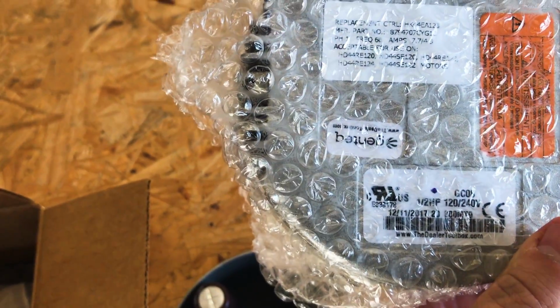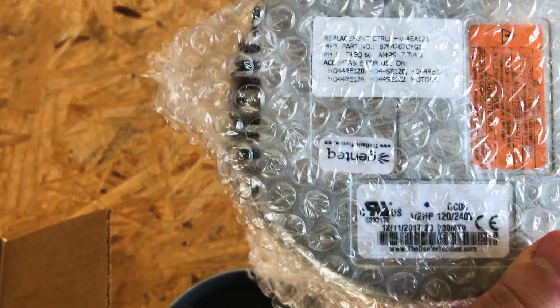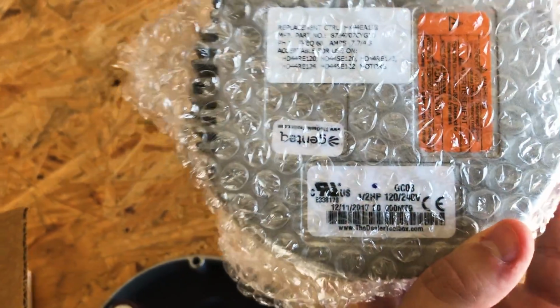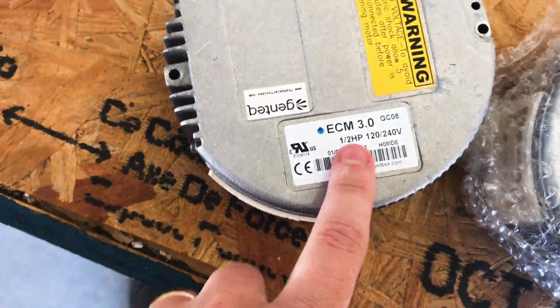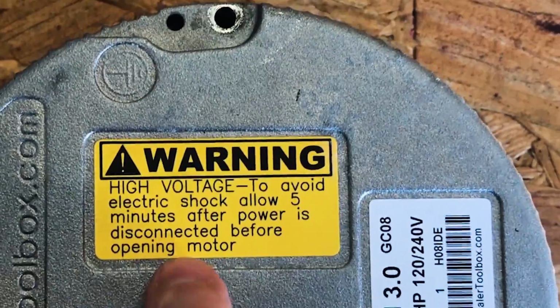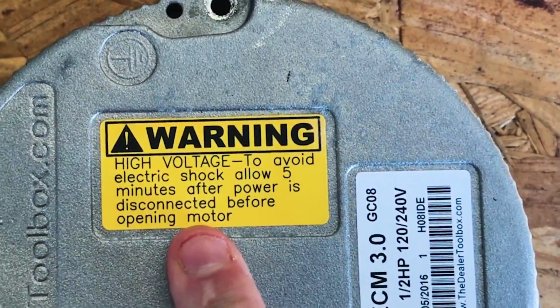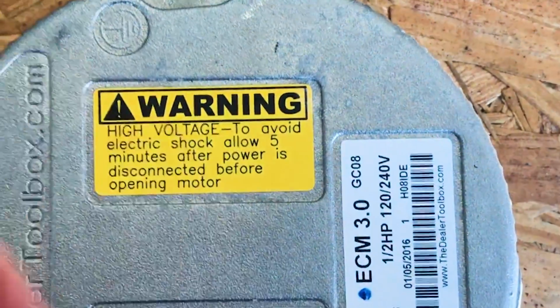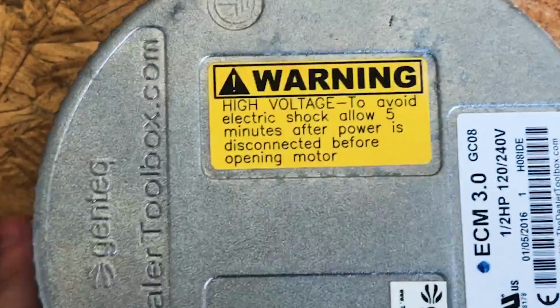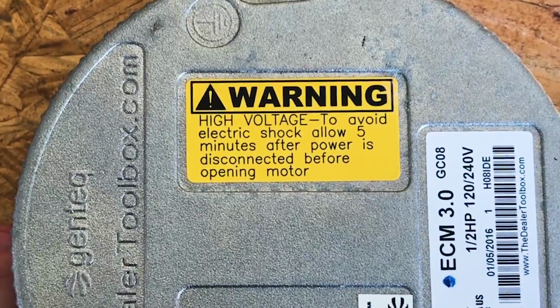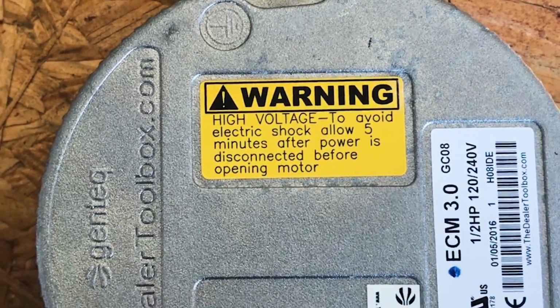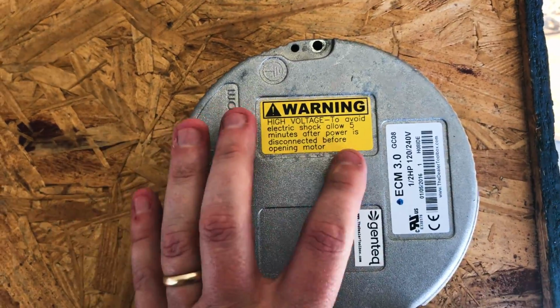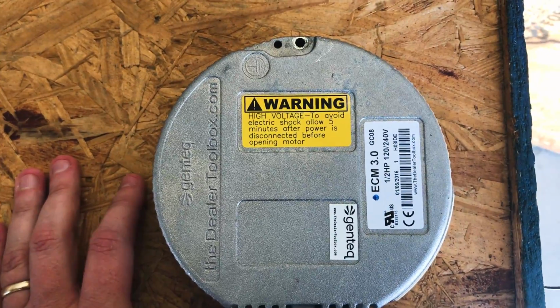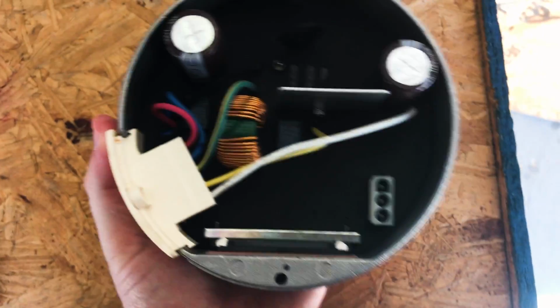ECM 3.0 motor. Of course, this one actually doesn't say ECM 3.0, the old one does, but you see right here it says ECM 3.0. Half horsepower, we are good to go. Whenever working with any sort of variable frequency drive, which is what an ECM motor module is, you always want to make sure that you leave it disconnected from high voltage for 5 minutes at least, and it varies unit to unit, but you want to make sure that it's been disconnected for a while before you go in there touching anything so you don't get a shock.